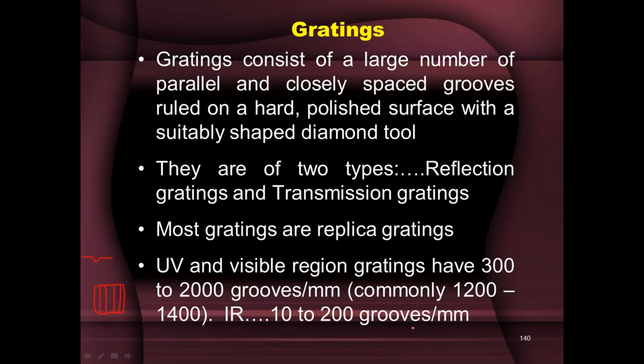For IR, the number of grooves is much lesser — just 10 to 200 grooves per millimeter — because IR radiation has much longer wavelengths. That is why a grating suitable for IR will not work for UV-visible instruments. In general, a grating chosen for shorter wavelengths is not suitable for longer wavelengths and vice versa. In a combination instrument, we take an intermediate value, commonly 1,200 to 1,400 grooves per millimeter.